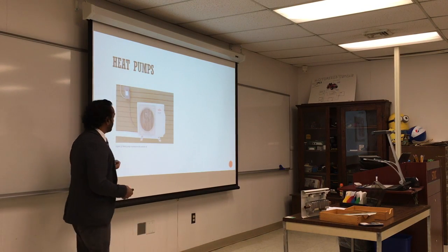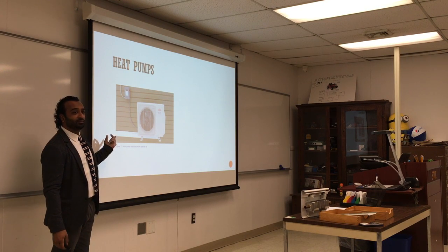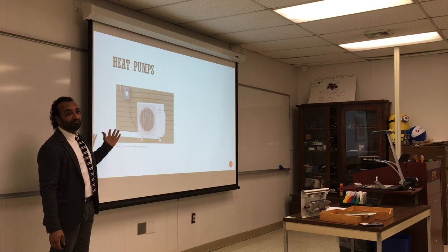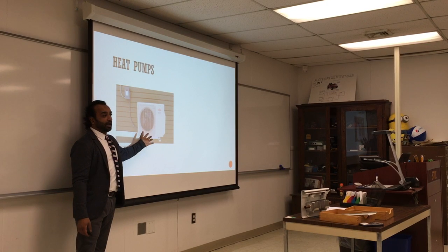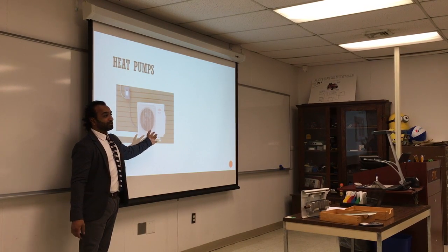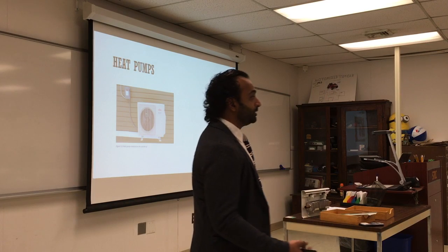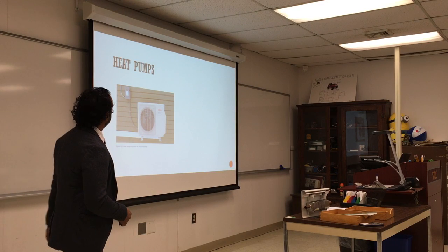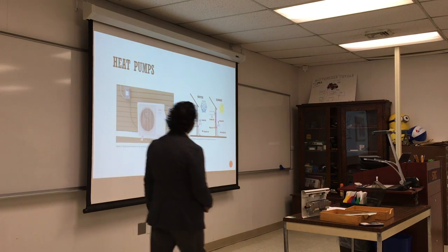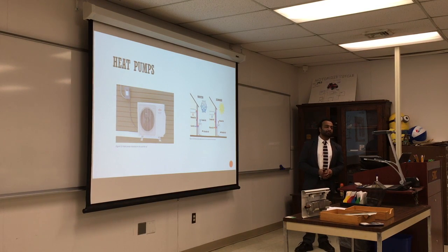So from the outside, it's very convenient. I still don't know how they handle those things on the third floor, but somebody came with a big ladder. Apparently they put some brackets on the outside of the building and you hang them, so you have the condenser in the summertime on the outside, and in the winter it becomes the evaporator. They became more and more efficient as the compression ratio got higher, and also as they came with new refrigerants. So yes, you can work both in summer and winter and provide you with heat within a reasonable temperature.